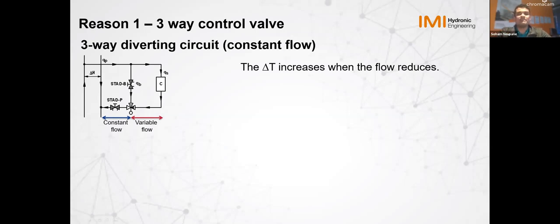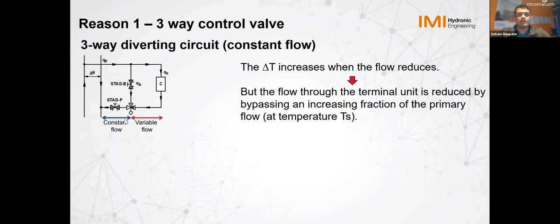But in this case, since we have a bypass here, if we don't want that flow through the coil because it's going to be variable, we're going to bypass the rest of the extra water through this bypass. Say we do not want any flow in this coil, we're going to bypass everything. So all the water is going to go through the bypass. And what are you getting? You're not getting any delta T at all. Whatever you're getting in your supply is basically going back to your return. And that's not good. In that case, your chiller's just going to do more work.